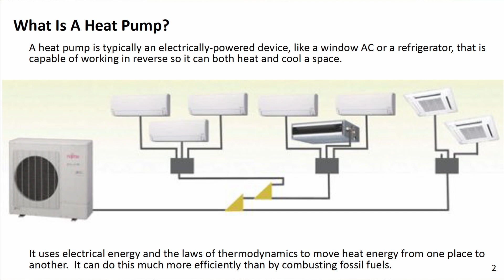When Lisa and her building were looking at heat pumps initially, several engineers told them that heat pumps were not acceptable as a heating and cooling setup because when it went below about 40 degrees outside, they had to revert to resistance electric heat, which is much less efficient. That was true 20 years ago, but a lot of engineers are not up with the times. For several years now, it's been possible for the equipment to operate in heat pump mode down to minus 13 Fahrenheit, much lower than what we see here in New York.